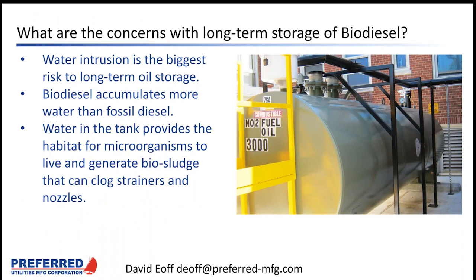Chemical degradation is important, but by far a larger concern is the accumulation of water in main storage tanks. These tanks are required to be vented to the atmosphere, and under certain conditions, the inside walls of the tank will condense water. The water is heavier than the fuel, so it will go to the bottom of the tank where it will sit. And it'll have fuel on top of it, so even on a warm, dry day, once that water gets to the bottom of your tank, it's never going to evaporate out. Also, the supply lines for your burners or your gensets should typically be up 6 or 8 inches, and hopefully the water doesn't get up to this level. But when you add more fuel to the tank, that water is never going to go away unless it gets sucked up by the intakes for your burners or your gensets, which is really the last thing that you want.